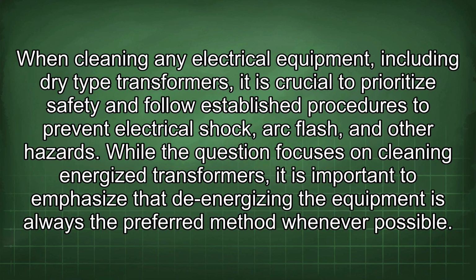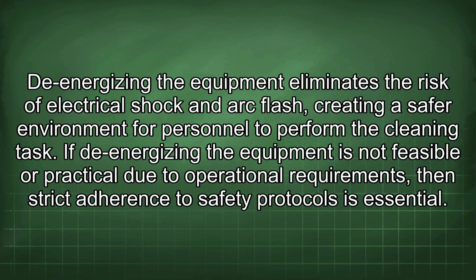When cleaning any electrical equipment, including dry-type transformers, it is crucial to prioritize safety and follow established procedures to prevent electrical shock, arc flash, and other hazards. While the question focuses on cleaning energized transformers, it is important to emphasize that de-energizing the equipment is always the preferred method whenever possible. De-energizing the equipment eliminates the risk of electrical shock and arc flash, creating a safer environment for personnel to perform the cleaning task.